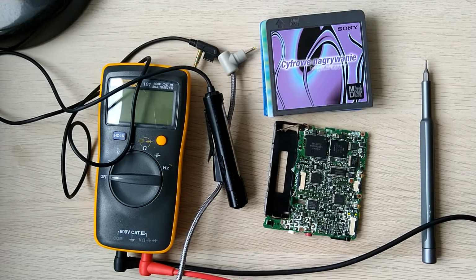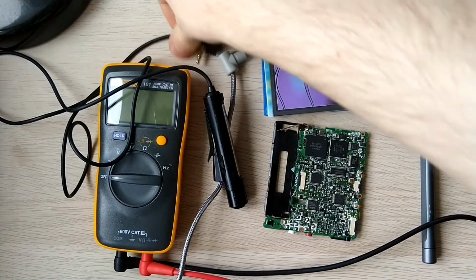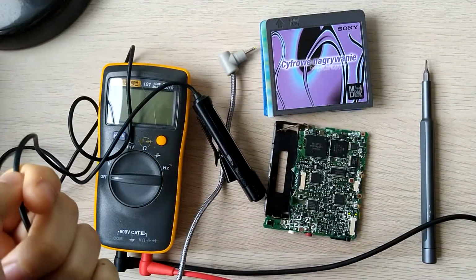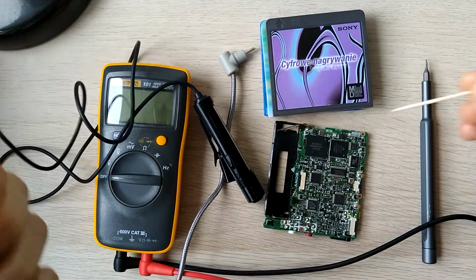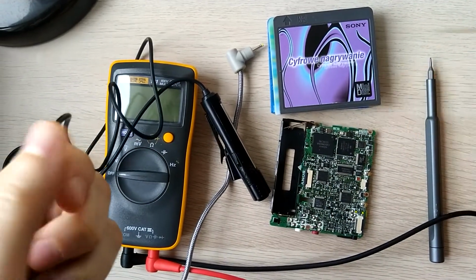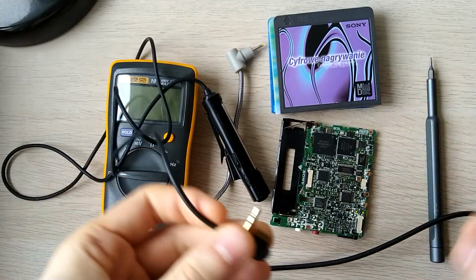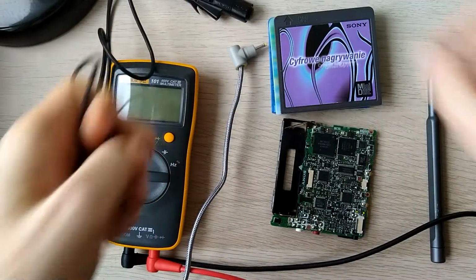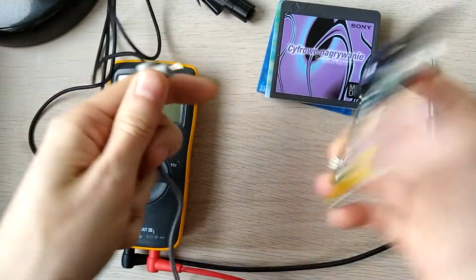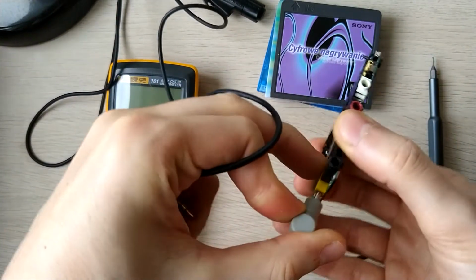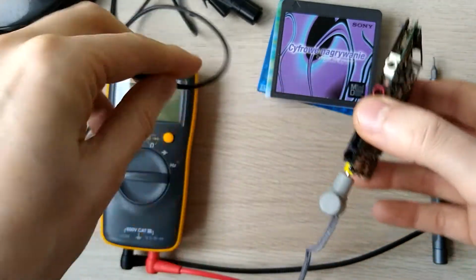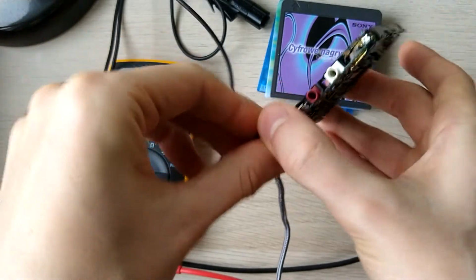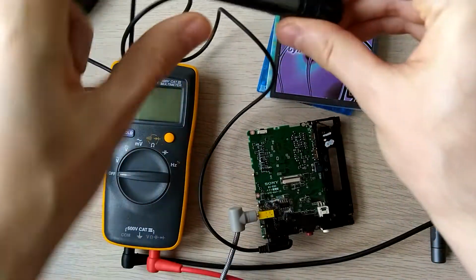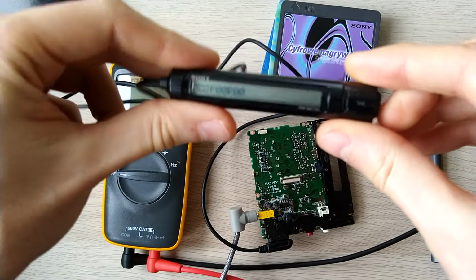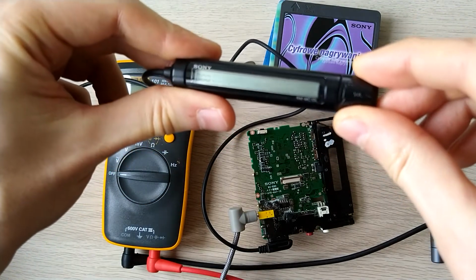So the first step is to put your device in service mode. When you have just the mainboard, the only way to do it is to solder the test point, which on this device is located here. And once it's soldered, the device will automatically start in service mode. So I'm just going to apply power. And as you can see, we are now in the service mode.